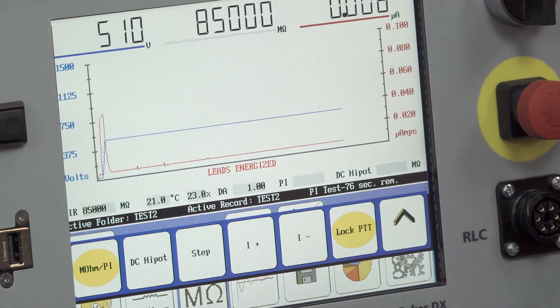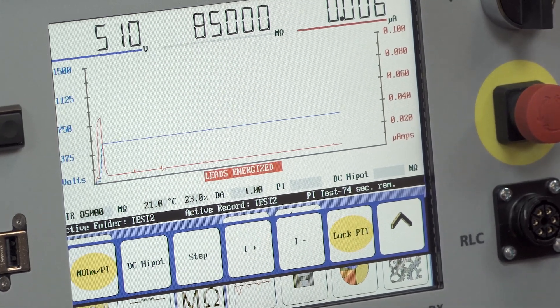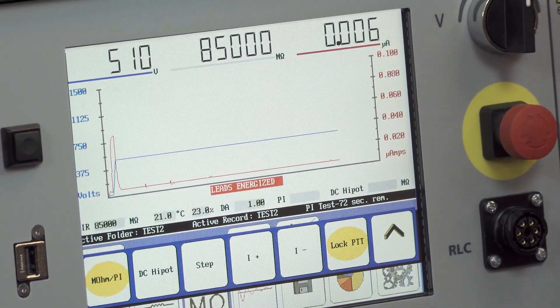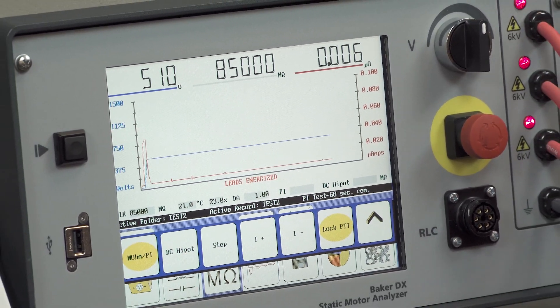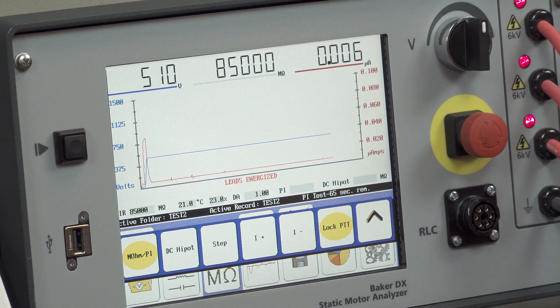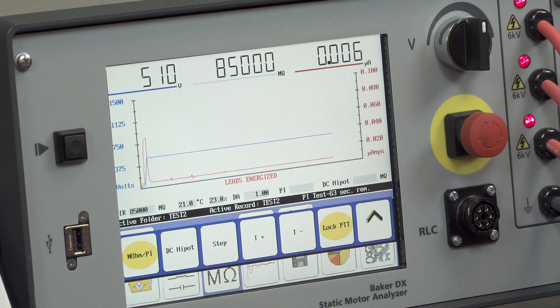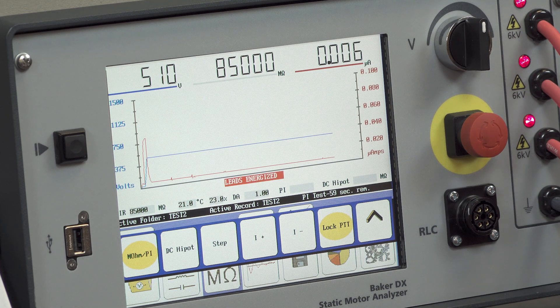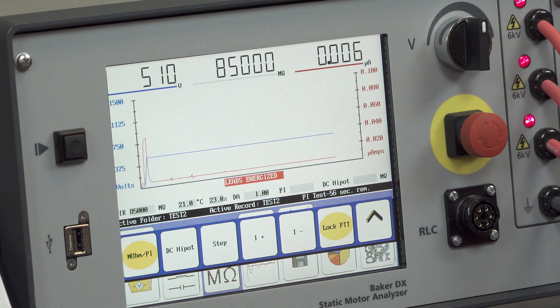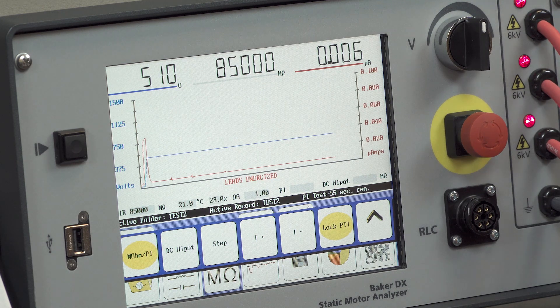From there we're going to naturally transition into our high potential testing, which could either be done as a conventional high pot where we'd ramp directly to test voltage and hold for one minute, or as I'll demonstrate in a step voltage high pot mode where we'll incrementally step in 500 volt increments in this case to 2,000 volts and then we'll hold for the final high pot.